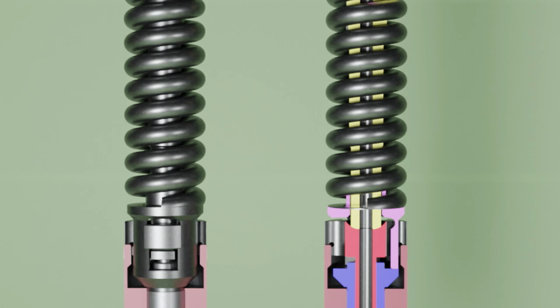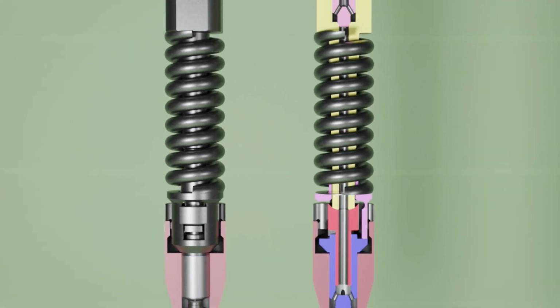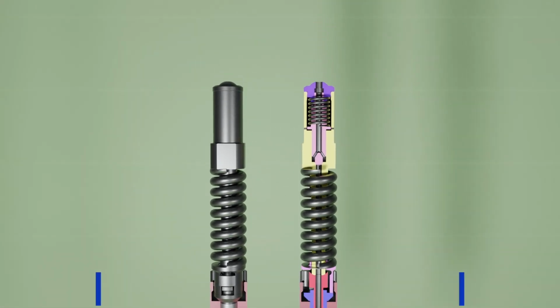Notice the contact surface between the thrust piece and non-return valve body. Leakage from here too will cause less fuel to be injected. These surfaces can be lapped with respective tools as per the maintenance manual to remove any scratches or imperfections. Non-return valve.